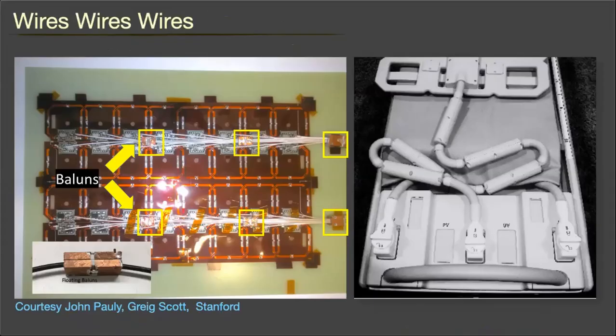The untold secret in the coil business is that most problems come from cabling. RF engineers spend most of their time routing cables and putting RF traps or baluns to minimize parasitic coupling to the elements and the body transmitter. This becomes a nightmare as the channel count increases. So this is, for example, a coil - you see all the cables, and what you have here are called cable traps.